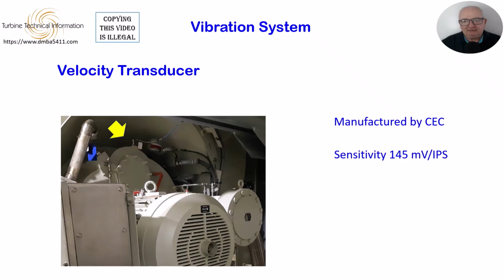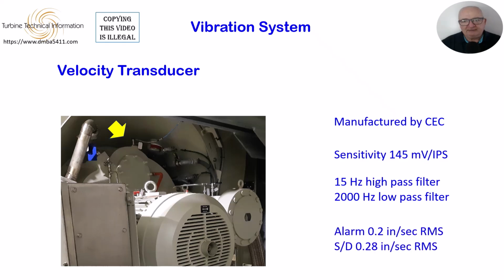Typically, the channel is set up with a 15 Hz high-pass filter and a 2000 Hz low-pass filter. This means vibrations lower than 15 Hz and higher than 2 kHz are filtered out. The alarm is set at 0.2 inches per second RMS and the shutdown at 0.28 inches per second RMS.